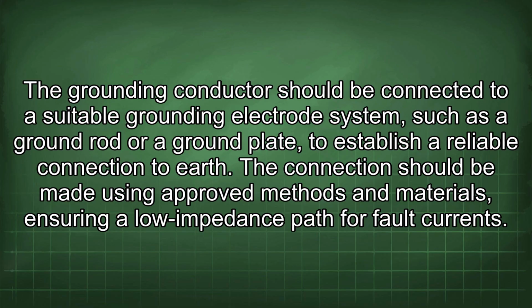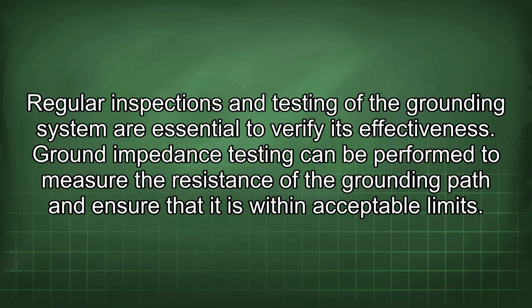The grounding conductor should be connected to a suitable grounding electrode system, such as a ground rod or a ground plate, to establish a reliable connection to earth. The connection should be made using approved methods and materials, ensuring a low impedance path for fault currents. Regular inspections and testing of the grounding system are essential to verify its effectiveness.